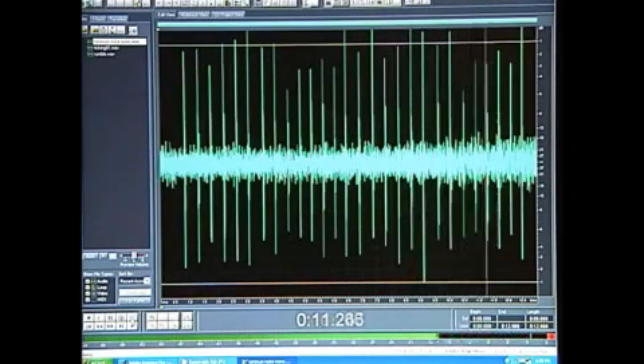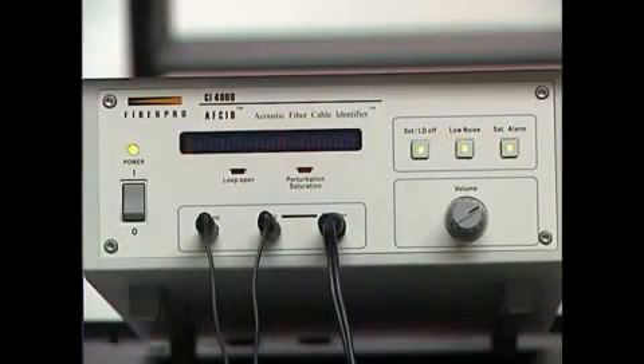In most situations, weak signals will not be a problem. In fact, the opposite is usually true. If you tap too hard on the cable, the signal can saturate. That is, reach the point where more force does not increase signal intensity. When this occurs, an LED on the front panel of the instrument will flash and a beep will be heard in the headset, indicating that the tapping is too strong. The field technician can then adjust the tapping force as needed.